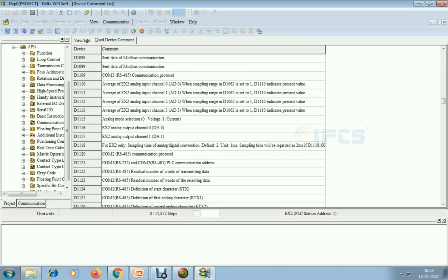The sampling time register is D1062 — I am giving one for the sampling time, like scan time. D1115 is analog mode — voltage or current. If I give zero it means voltage mode, and one is current mode. So first I'll set the sampling time and voltage mode.